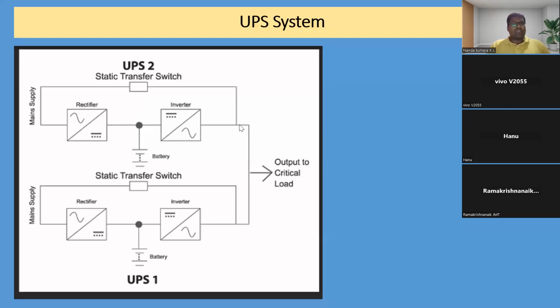then something goes wrong. In a parallel UPS, the manual bypass or maintenance bypass will not be enabled. Generally, a maintenance bypass will be there, but for some other technical reason it will not be enabled. It will be only either UPS 1 or UPS 2 that gives the output. A number of UPS can be configured, probably a maximum of 5 or 6, based on the different capacities and technologies available.